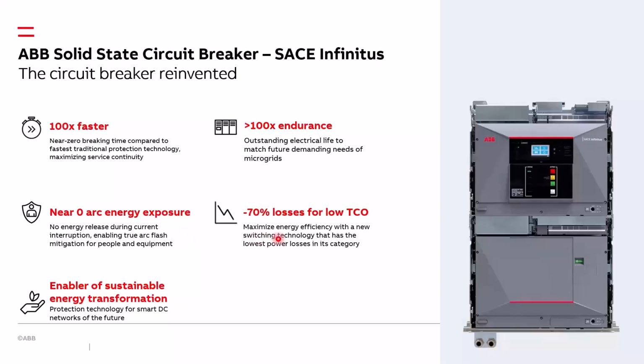Compared to other existing solid-state technology, thanks to the internal architecture made by IGCT, which is the integrated gate commutated thyristor, it has lower power losses compared to, for example, other technologies like IGBTs. And thanks to this solid-state circuit breaker, we can enable the DC distribution inside any DCI, but also, for example, inside buildings, also on board of ships.